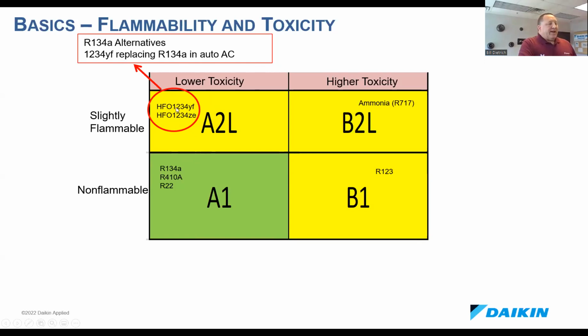The 1234YF gives you about the same capacity as 134A, but is not quite as efficient. But this is the one you're typically going to see in your automobile AC now, because since the capacity is similar, that compressor under the hood doesn't have to get any bigger. In the HVAC world, we're more interested in the 1234ZE because this has efficiency similar to the 134A, but if you just drop it in a 134A system, you can lose up to about 25% of your capacity because you have to circulate a little higher CFM per ton of cooling than you did with 134A.